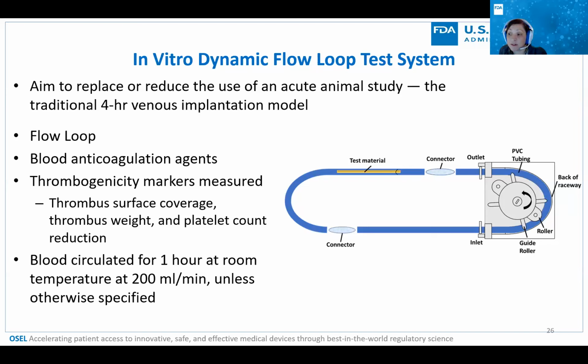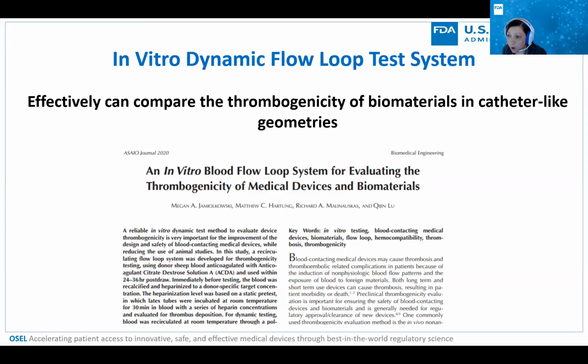And then thrombogenicity markers can be measured once your blood has been circulated for an hour at room temperature under these conditions. They have thrombus surface coverage, thrombus weight, and also platelet count reduction that can be measured for a particular material. This is a catheter geometry for this particular tabletop setting, so this can be used in early stages to evaluate any test materials that may be of interest for your medical device. So this is a way that you can effectively compare the thrombogenicity of biomaterials in a catheter-like geometry. All of this was published in a paper in 2020 that can be reviewed. It's also on our catalog for your reference, if that is of interest to your particular medical device as well.